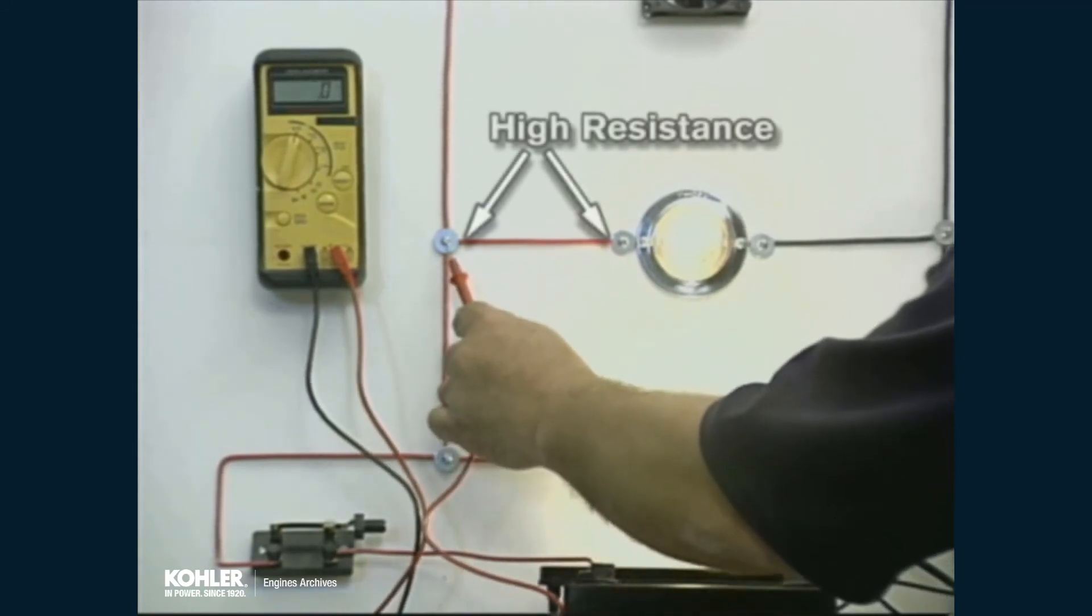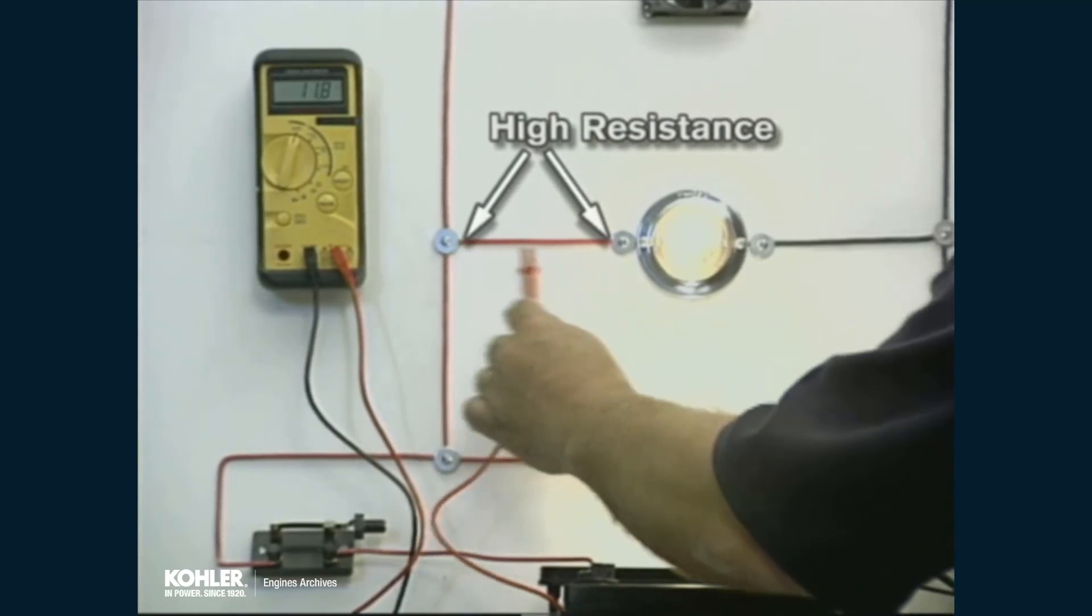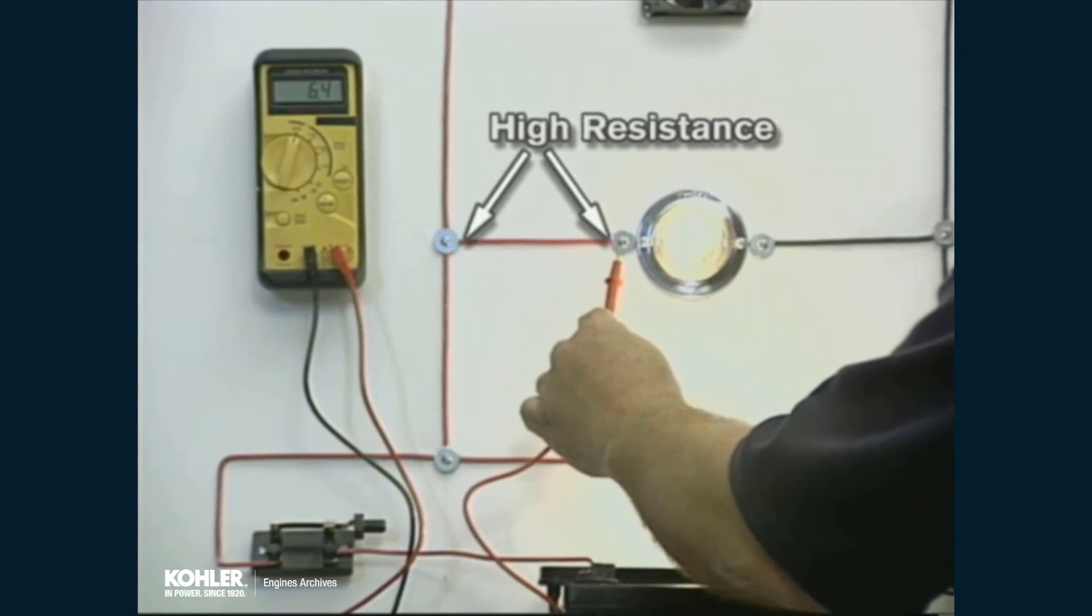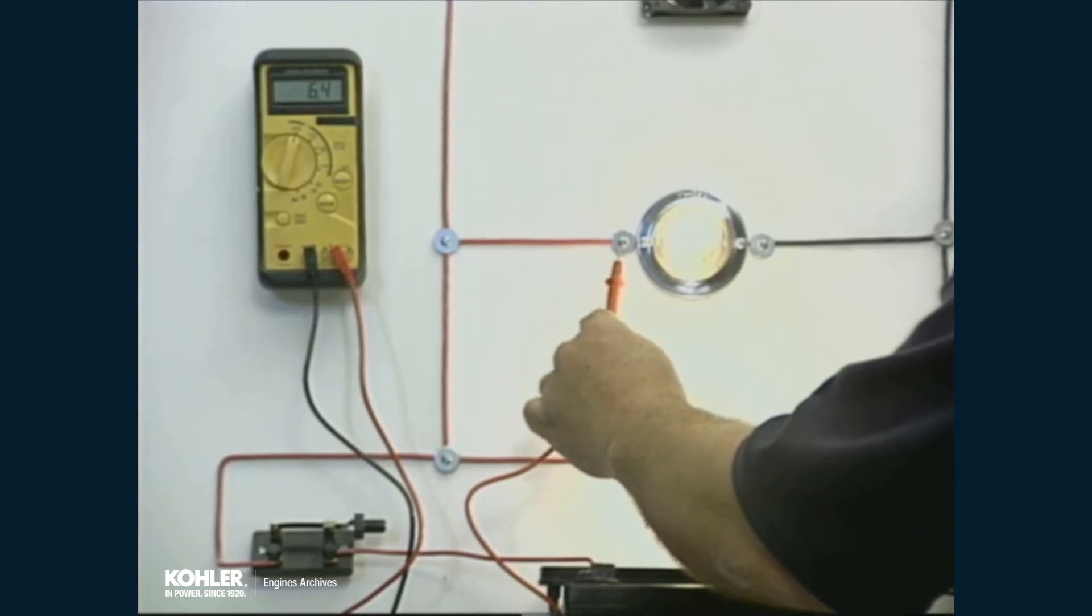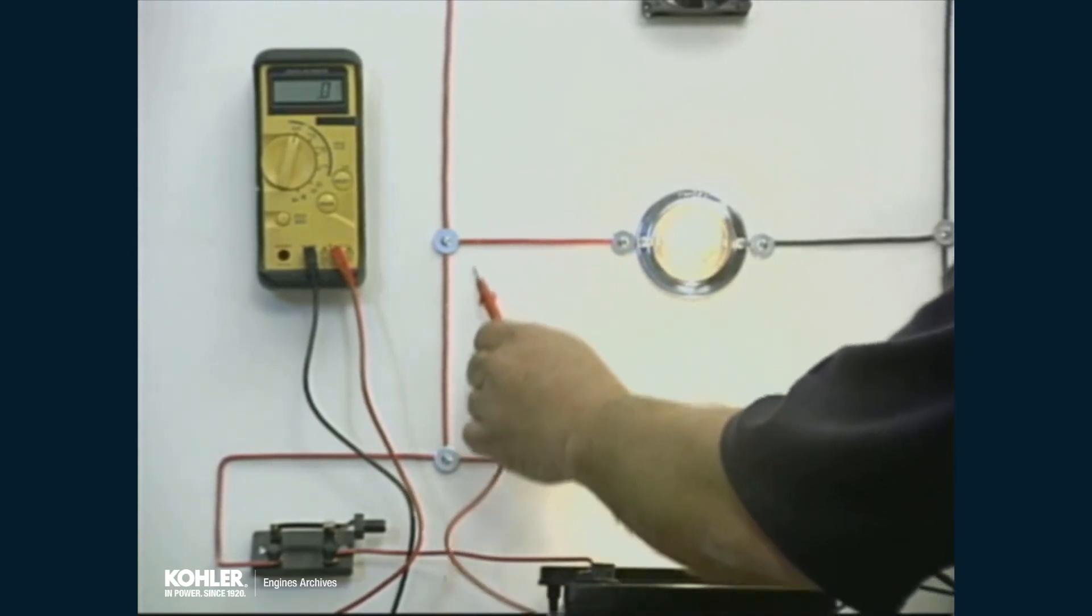However, if a high resistance exists in the circuit between the voltage source and test point, a reduced voltage will be observed between the resistance and ground. Taking readings at various points will allow identification of the resistance by narrowing down the section between normal and low readings.